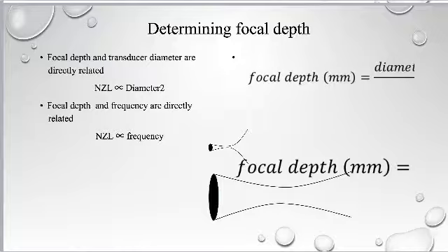So on an image with the focal depth, when it changes the focal depth so that it slides up and down, right, that makes sense? Yeah. Looking at an image, your focus is always going to be, because it tapers down, right? But when we set our focus on a machine, typically our image is like this, and that focus pretty much clears up everything, that whole section. So how does that work, since the tapering's reversed on the image versus the beam? I'm going to try to draw a picture, but I'm just going to preface it by saying I'm not exactly sure what you're talking about, but I think if I draw a picture, it'll make sense to all of us.